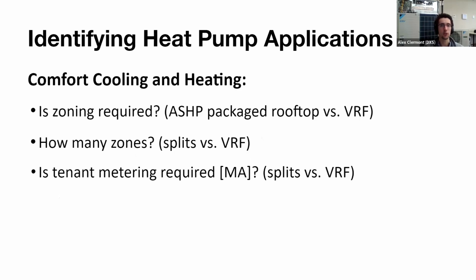Now, in terms of comfort heating and cooling applications, how do you actually decide what you want? It all starts with the zoning. Remember, VRF and split systems are zoning systems. So, for example, if you have a gym, a central air source heat pump rooftop package unit would be a little bit of a better option over a VRF system. Now, if zoning is required, how many zones? For a small number of zones, split systems might do, but VRF might be a better option for a larger number of zones. Another question to ask in Massachusetts would be whether tenant billing or tenant metering is required. In Massachusetts, for a residential rental building, you're not allowed to meter VRF and charge tenants. So one-to-one split systems are a bit of a better option, and we see a lot of developers going that way, one-to-one, for the rental market.